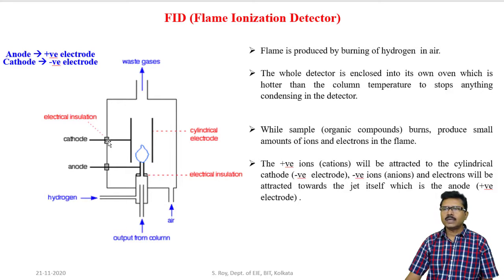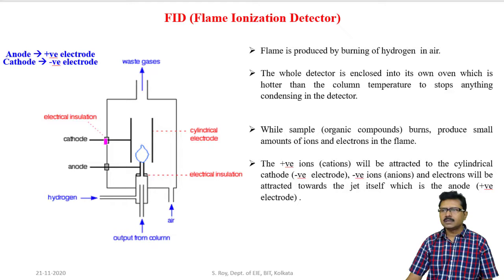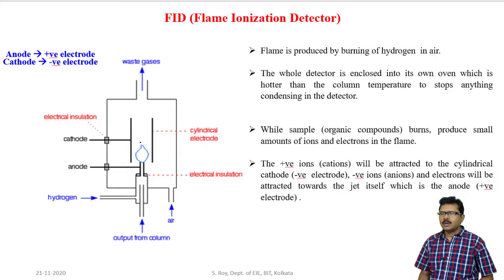In the detector there are two electrodes — one is cathode and another one is anode. The anode is the positive electrode and cathode is the negative electrode. In the external circuit, anode is connected with the positive terminal of the battery and the negative terminal is connected with the cathode. The cylindrical jet acts as the anode and the upper cylinder acts as a cathode. When sample enters through the jet and is burnt by the flame, that sample will form positive ions, negative ions, and electrons.